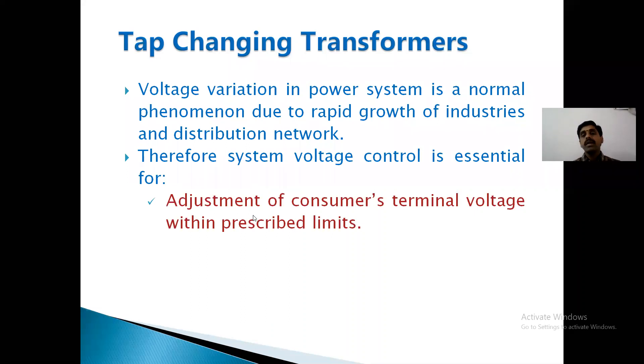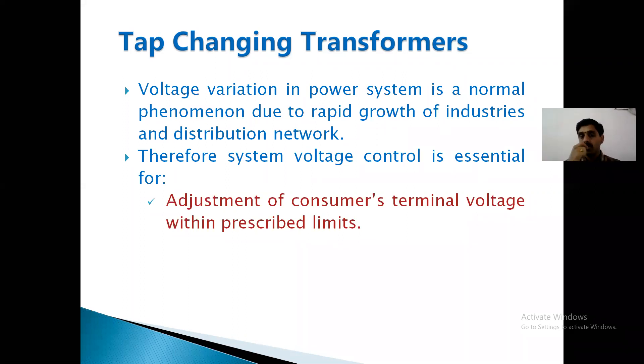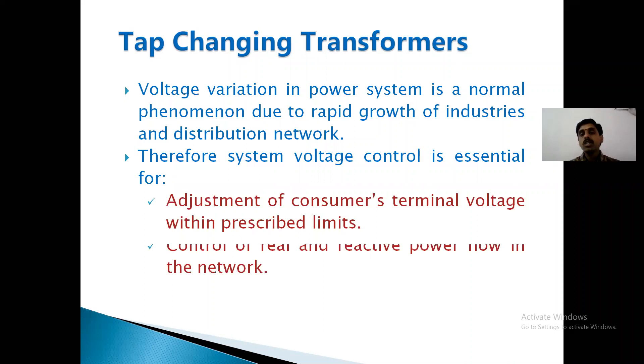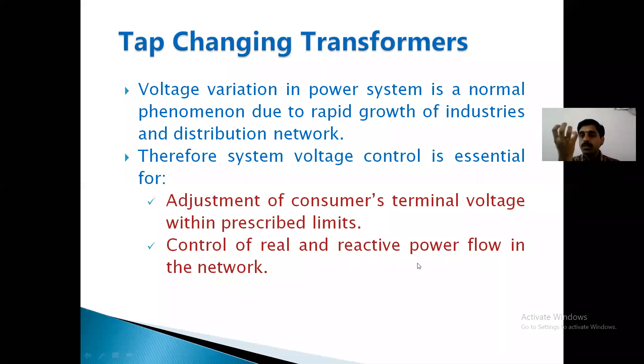Voltage control is needed for adjustment of the consumer's terminal voltage within prescribed limits — we have to adjust the voltage within plus or minus 5% variation; it should not vary above or below that. Next, the control of real and reactive power flow in the network. If you want to control reactive power especially, voltage must vary — more absorption of reactive power means more voltage to be supplied; less absorption means voltage should be reduced.